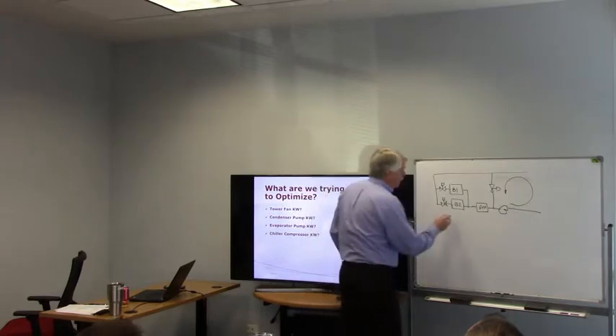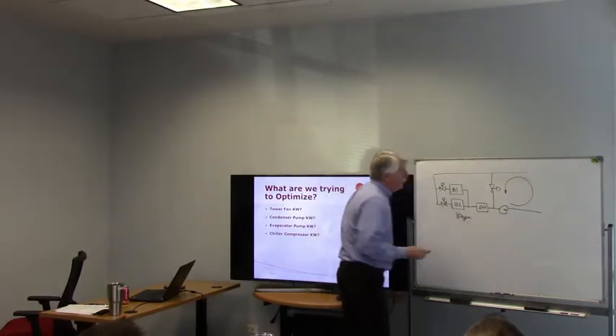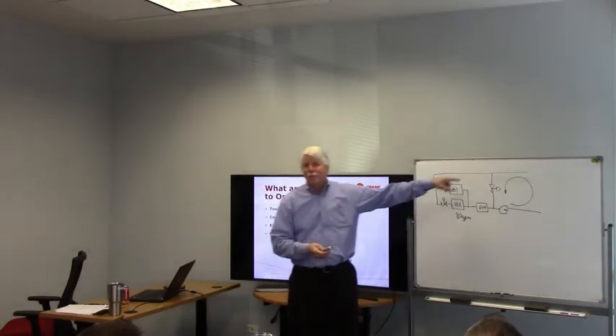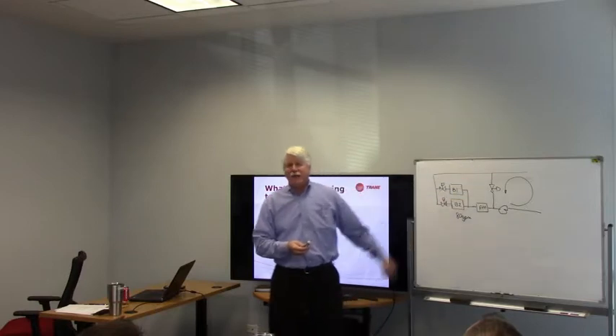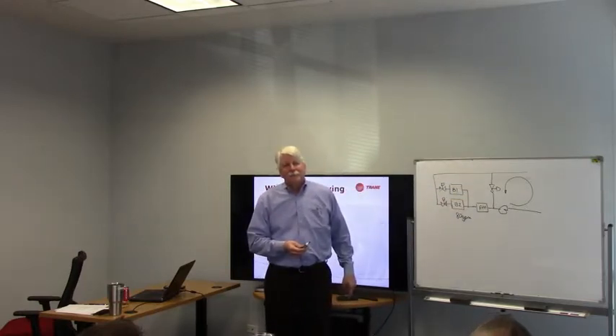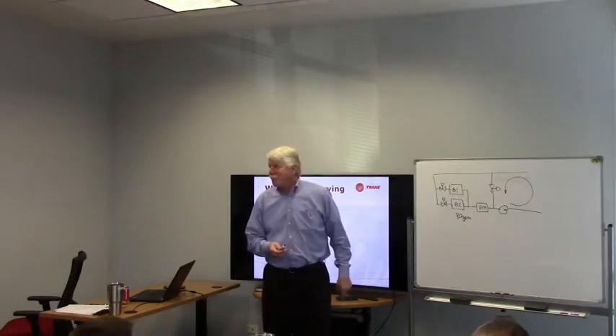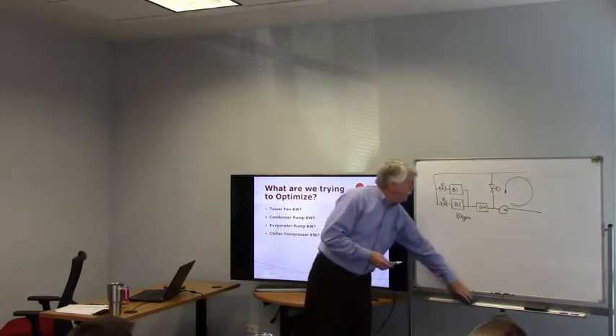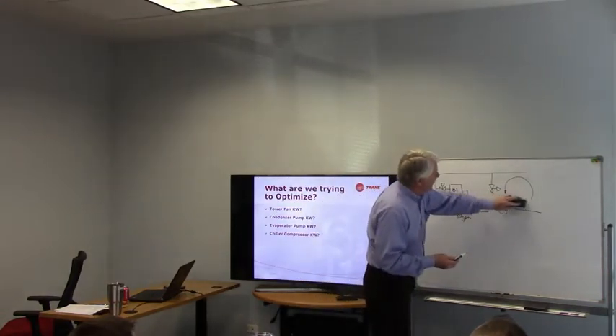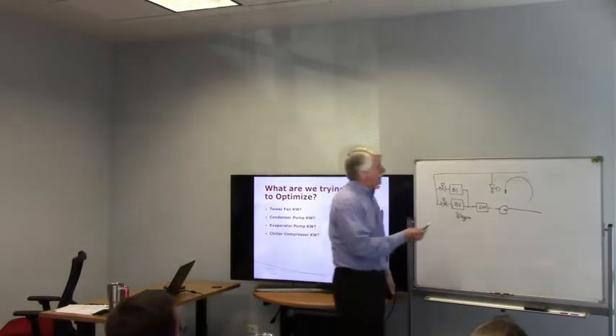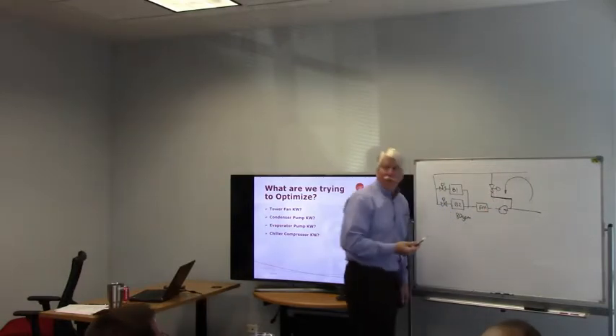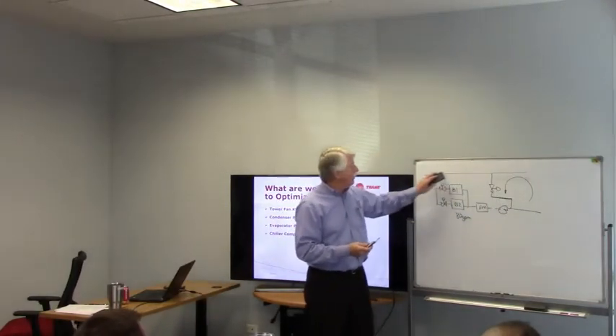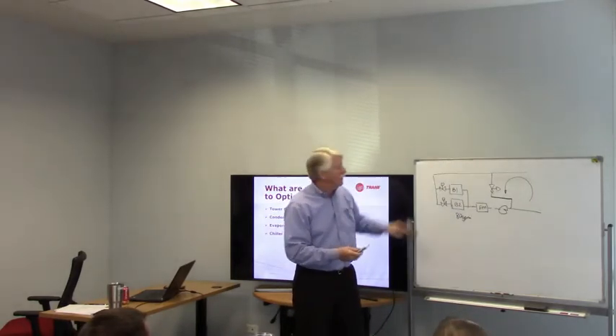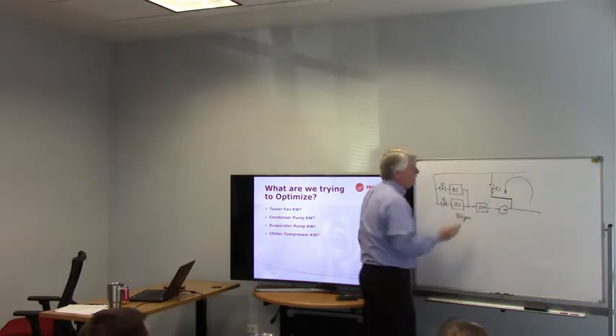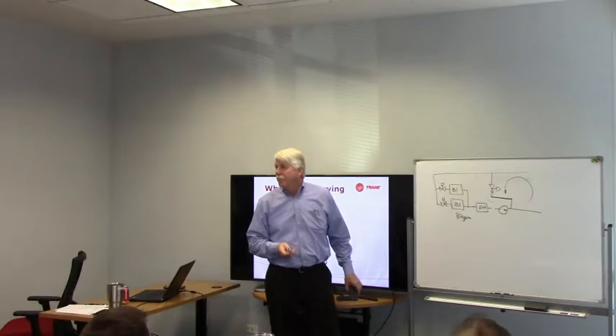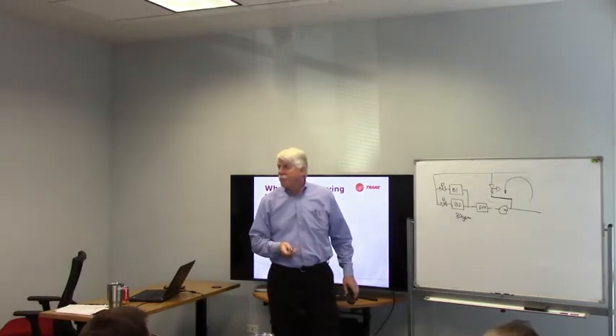So in other words, let's say these were like 80 GPM. And every time these boilers would go above 80 GPM, the bypass would open up a little bit, and they'd stay at 80 GPM. Everybody see that? And the only way to fix that is you've got to take the water under the high pressure that's headed back to the system and connect it back to the inlet of the boilers that way. So now it's pushing water this way, and now the water goes like this when you open the valve. And now you can maintain minimum flow on the boilers. But before we couldn't maintain minimum flow. Okay?